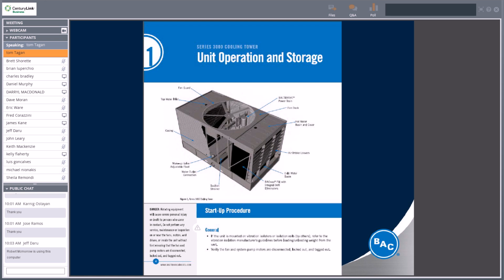The Series 3000 cooling tower for BAC is their dual air inlet induced draft prop fan cooling tower. This is really the workhorse of their entire product line, very similar to the Marley NC and the Evapco AXS product. So this is on most projects in New England, significant-sized towers. You're going to see this on 60 to 70% of the projects in the area. I know I was recorded on the first one, so it'll be interesting to see if my percentages compare there or not.